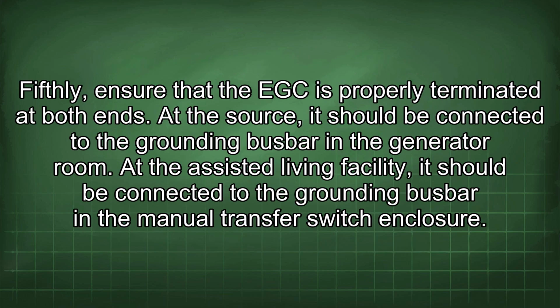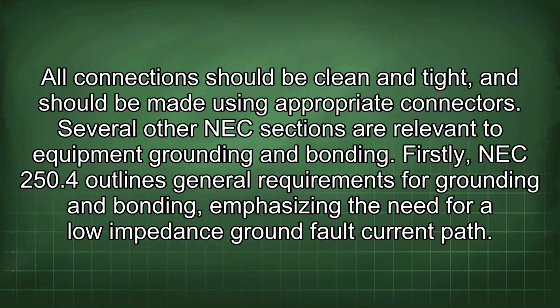Fifthly, ensure that the EGC is properly terminated at both ends. At the source, it should be connected to the grounding busbar in the generator room. At the assisted living facility, it should be connected to the grounding busbar in the manual transfer switch enclosure. All connections should be clean and tight and should be made using appropriate connectors.